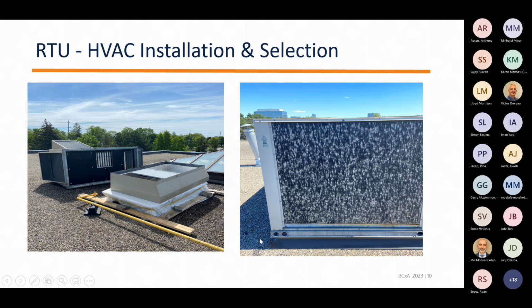There's one here. It's an upgrade when you order an RTU, and this is a bit of a legacy thing, going back in the day where they didn't think to order hail guards, and I get up on the roof and I see the damage from hail. Good heavens to Betsy. Not good on performance. And you'll notice how close it is to the ground, where this one's way up. This is up nice and high. That's good, you want to keep the coils clean.